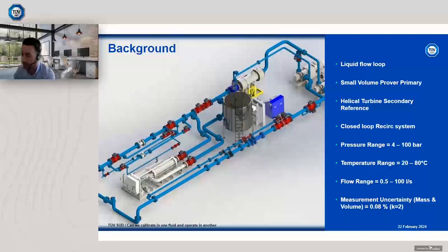So as such, we designed a closed loop system that you can see on the screen. It utilises an Emerson compact prover, that's now the Brooks compact prover, 60 litre version, and 3 helical turbine devices. And then we have 2 test sections that you can see at the bottom of the screen. The facility operates from 20 to 80 degrees Celsius, from 4 bar to 100 bar gauge. We can keep temperature stability to nominally about 0.1 to 0.2 degrees C through a calibration, and the pressure to nominally 0.1 to 0.2 bar throughout the entire calibration. It's very good temperature and pressure stability.